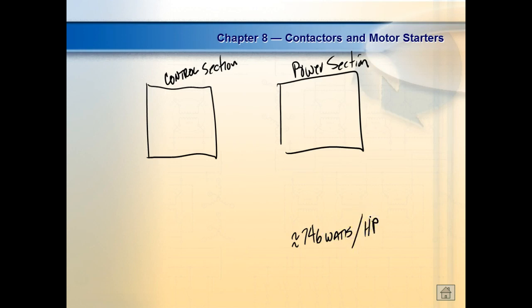And why is that important though? Well, over here in the United States, using what we call the Imperial Standard of Measurement, we use horsepower. The rest of the world uses watts. So a lot of times now when you look at a nameplate of a motor, it's going to say like 10 horsepower, 7.5 kilowatts. And of course, the kilowatts makes more sense because that tells me approximately how much wattage that motor is going to need to run, right? Don't you think? So if I have a 10 horsepower motor, then that would be 7.5 kilowatts. That makes sense.